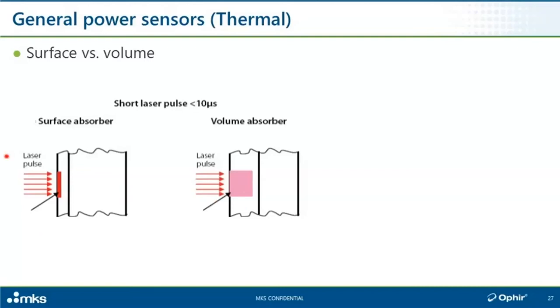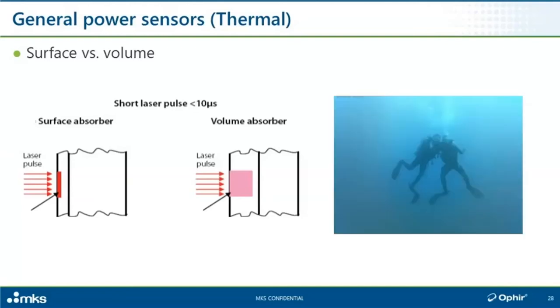A good example of a volume absorber is neutral density absorptive glass. It absorbs light incrementally as the light moves through this partially transparent material, so that even for an extremely short pulse, the heat is distributed through a much thicker layer of material — you don't have one layer that has to contain all of this heat. If you want an image of light being absorbed incrementally as it moves through material — like light coming down through water at 12 meters depth, being incrementally absorbed — that's exactly the principle. Some of our sensors are based on surface absorbers and some on volume absorbers. Volume absorbers are really good for very short pulses with high energy density, but they're not very good for high average powers. There are always trade-offs; the sensor finder will do most of the thinking for you.